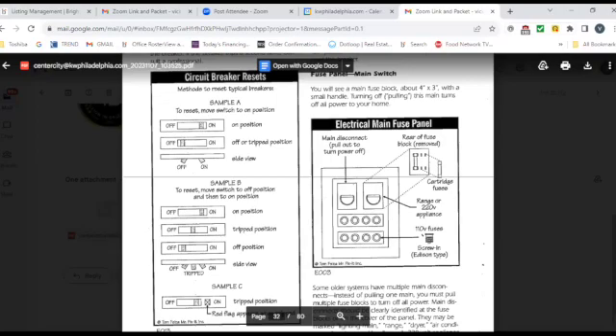A third type of manufacturer tripping scenario would be a red light indicator. You run down the steps and see that even though the breaker is all the way to the right, there's a red flag identifying that it had tripped. Again, you take your thumb, push it to the left, and then turn it all the way to the right — that will reset it for you.